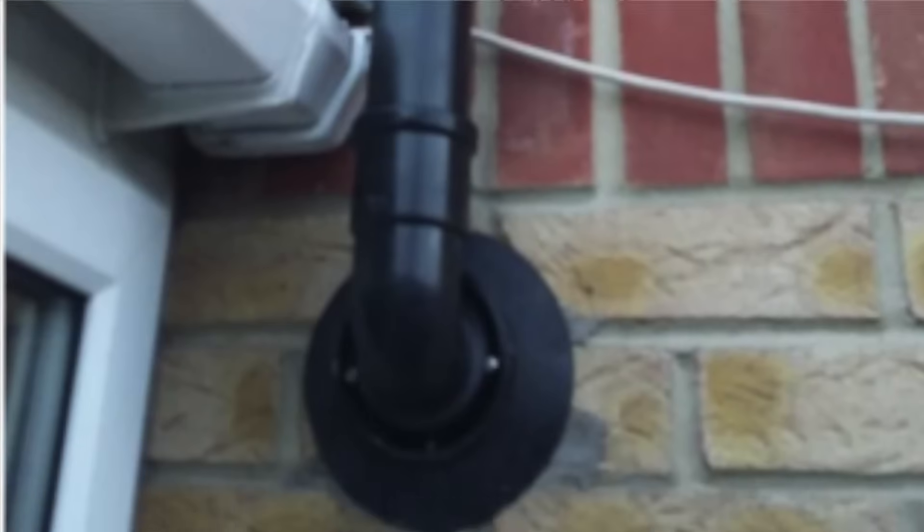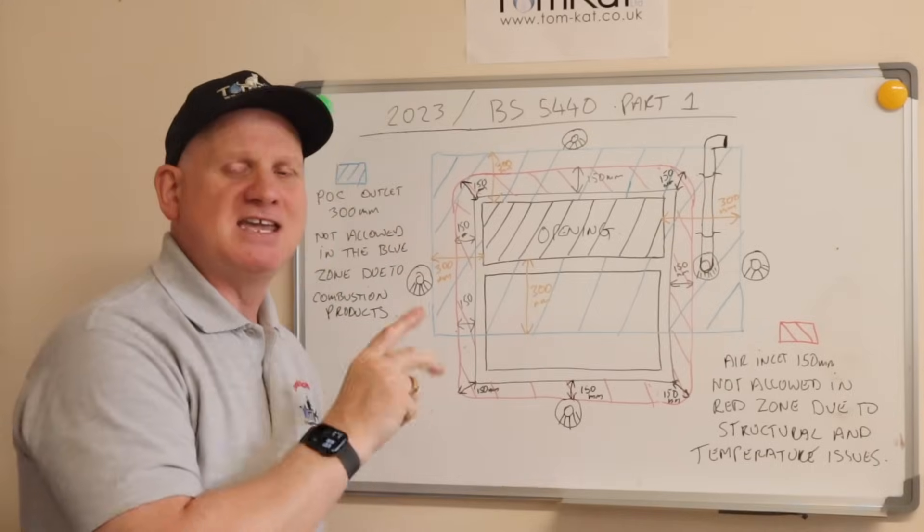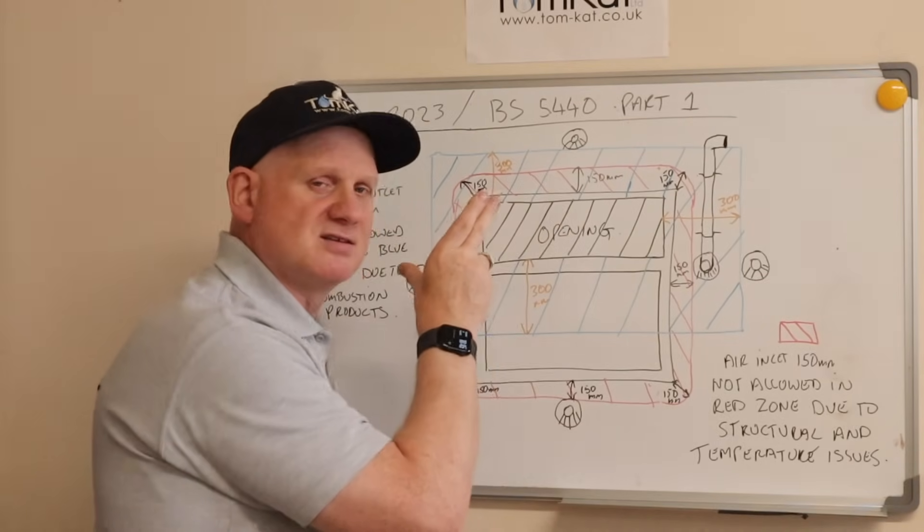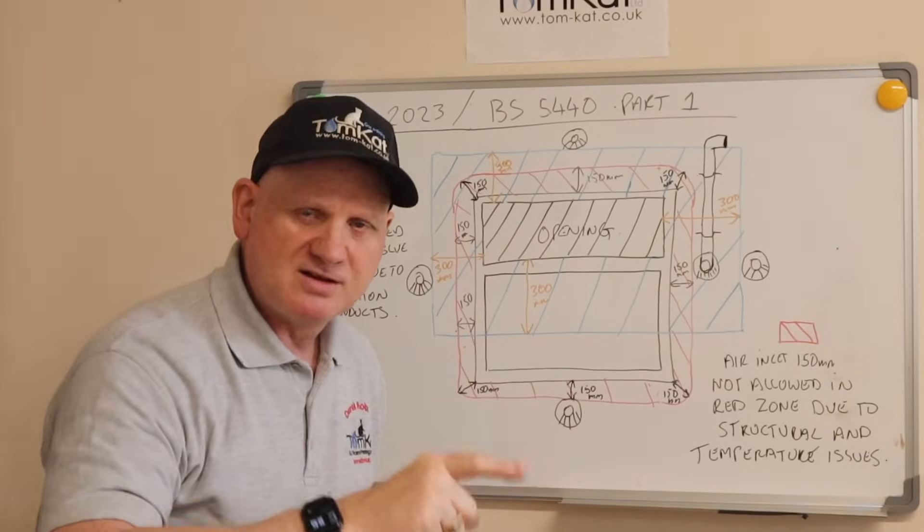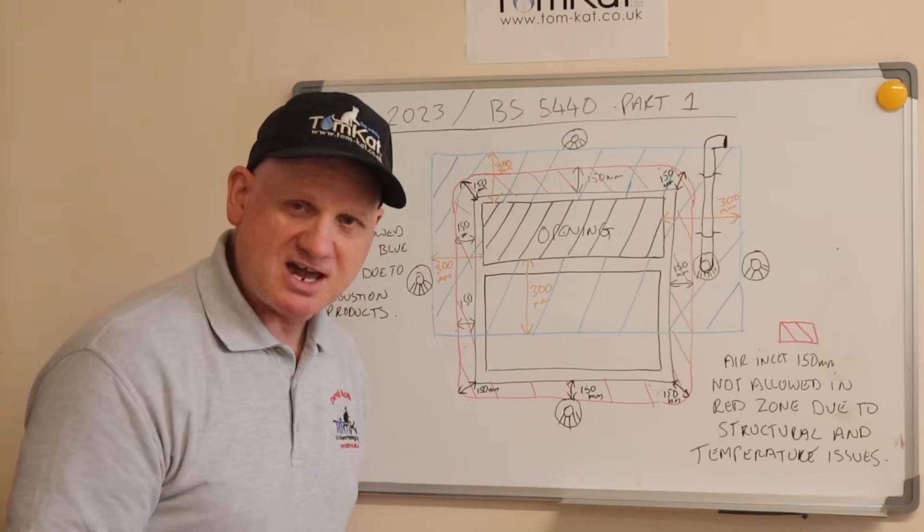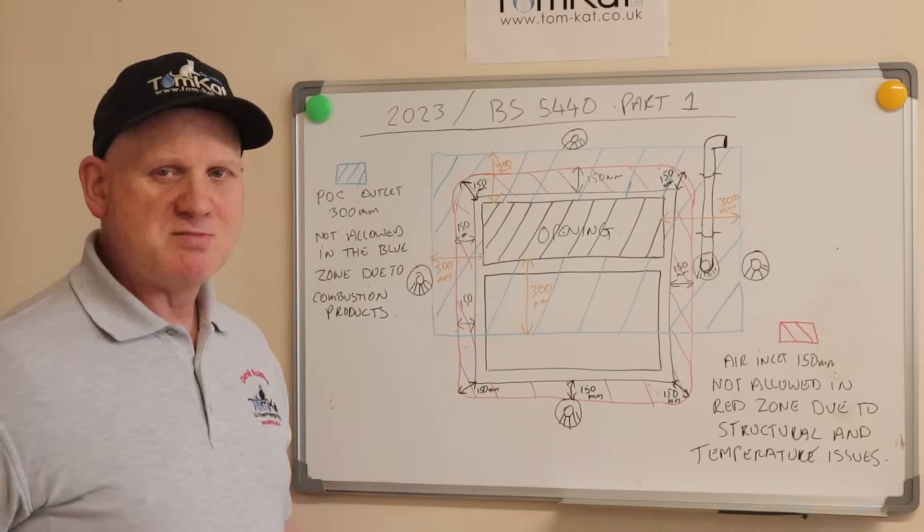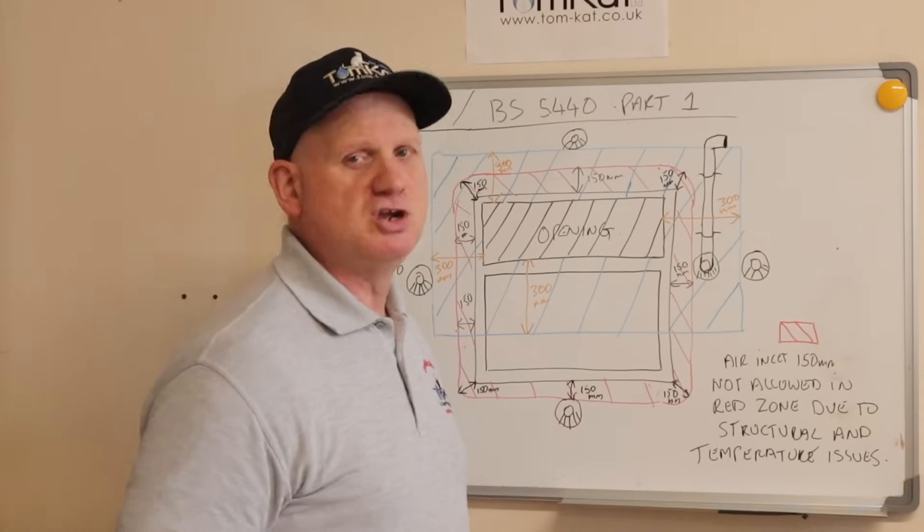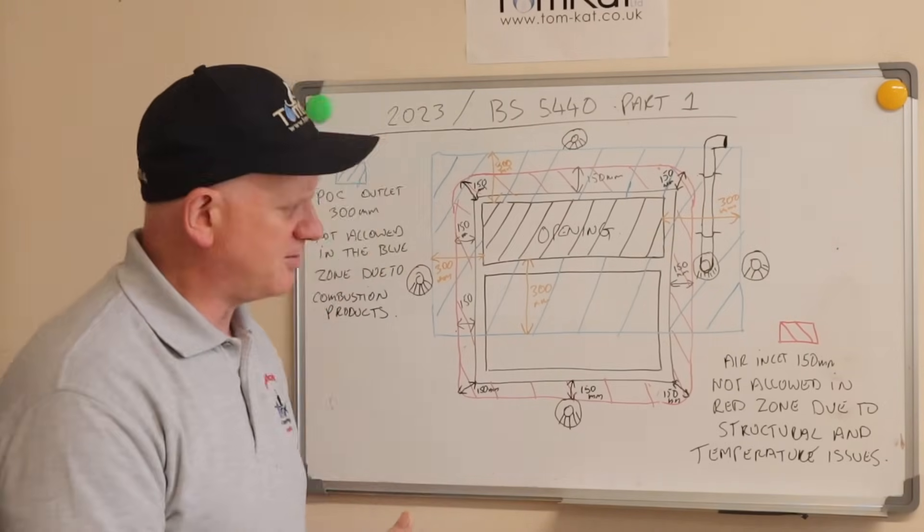Now the reason why BS 5440 says away from the frame from this one is this little statement here, where it says air inlet 150mm not allowed in the red zone due to structural and temperature issues. Because not every boiler allows you to do this, most of them do, but not all of them.